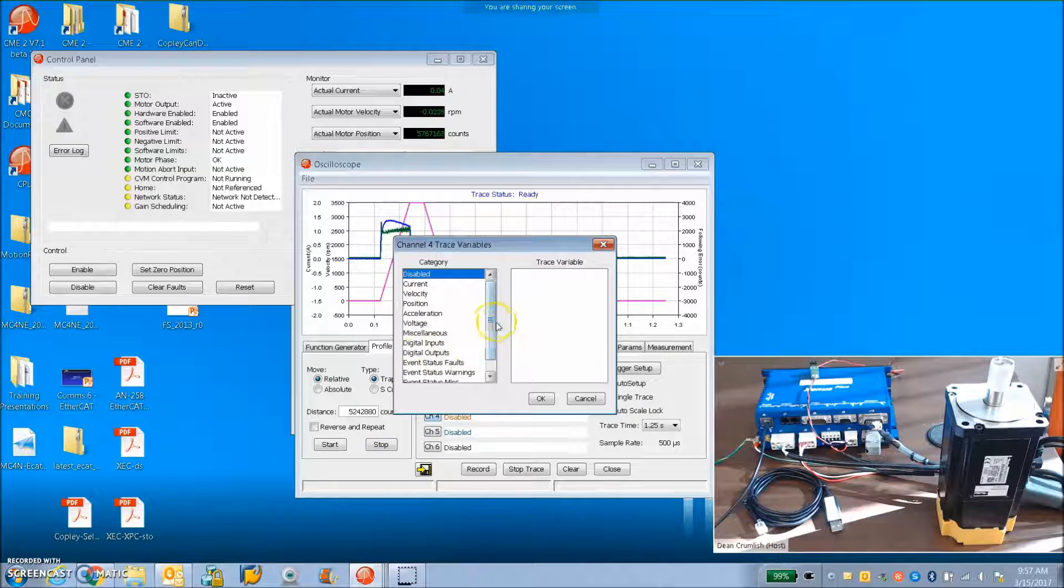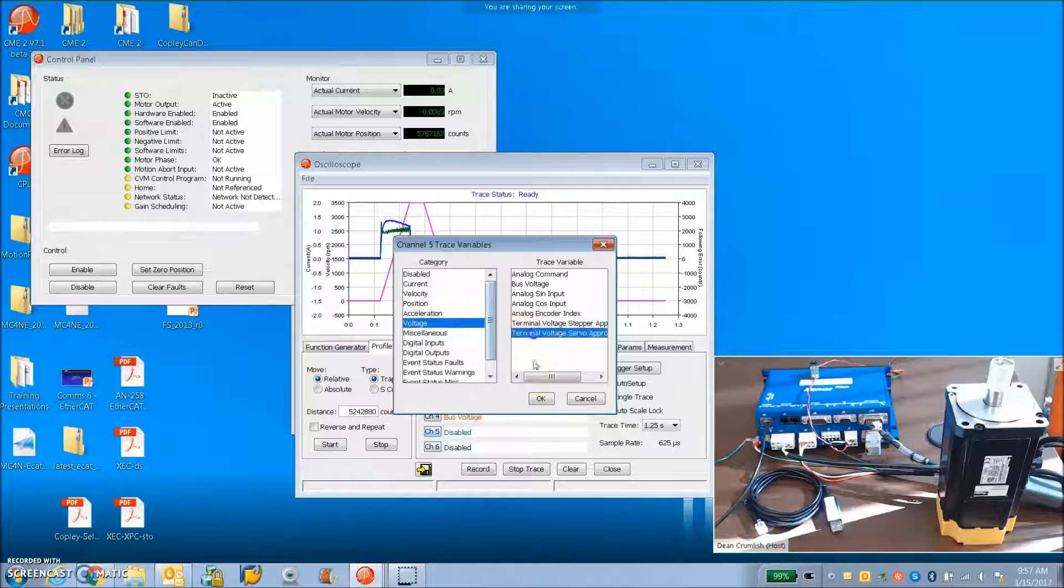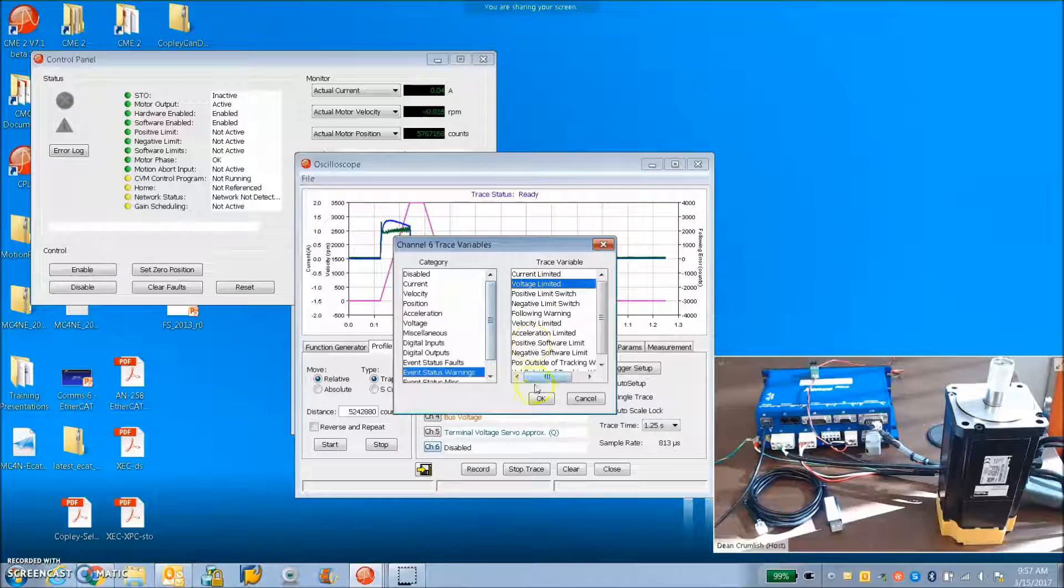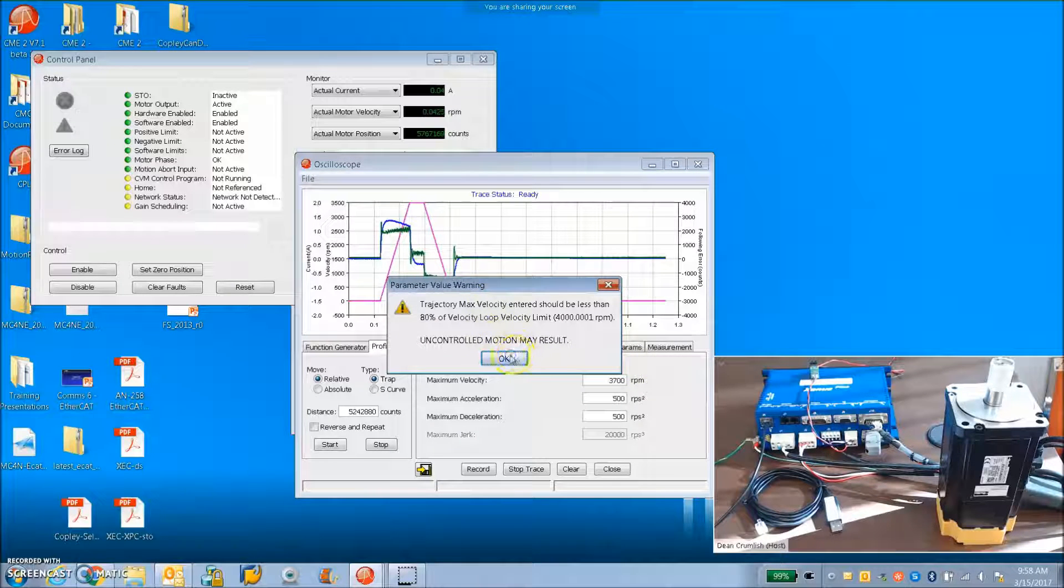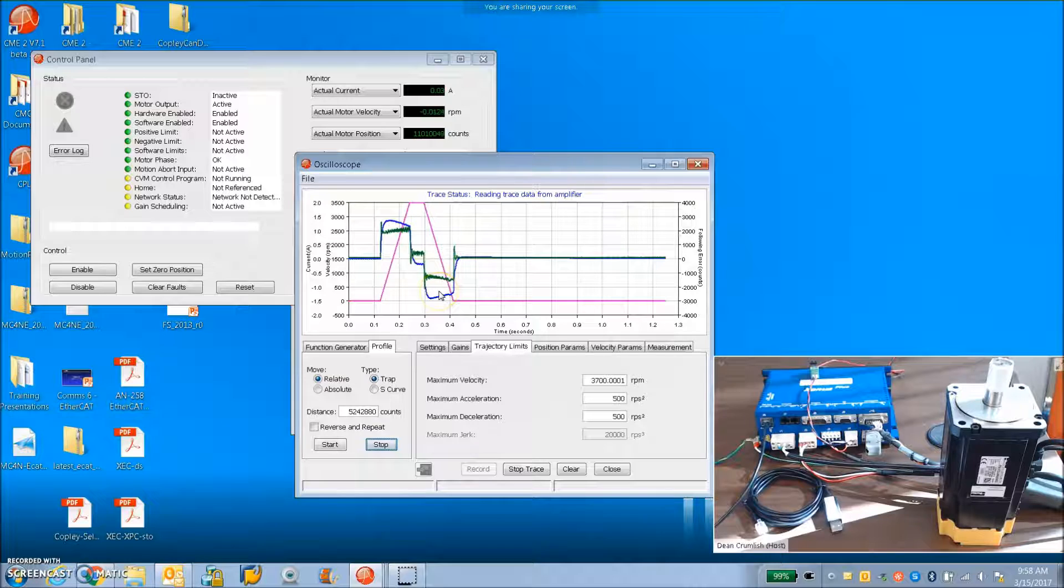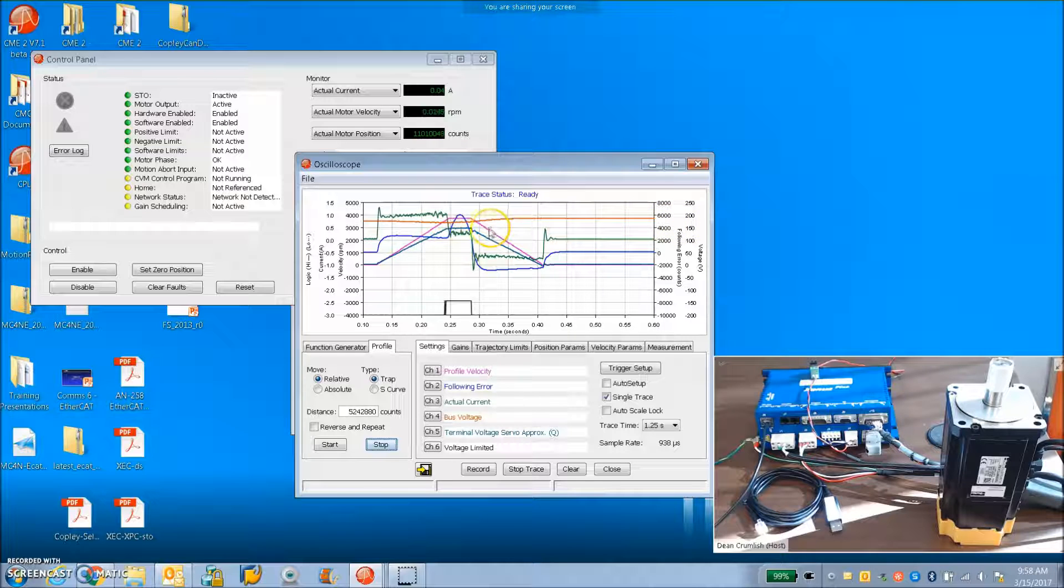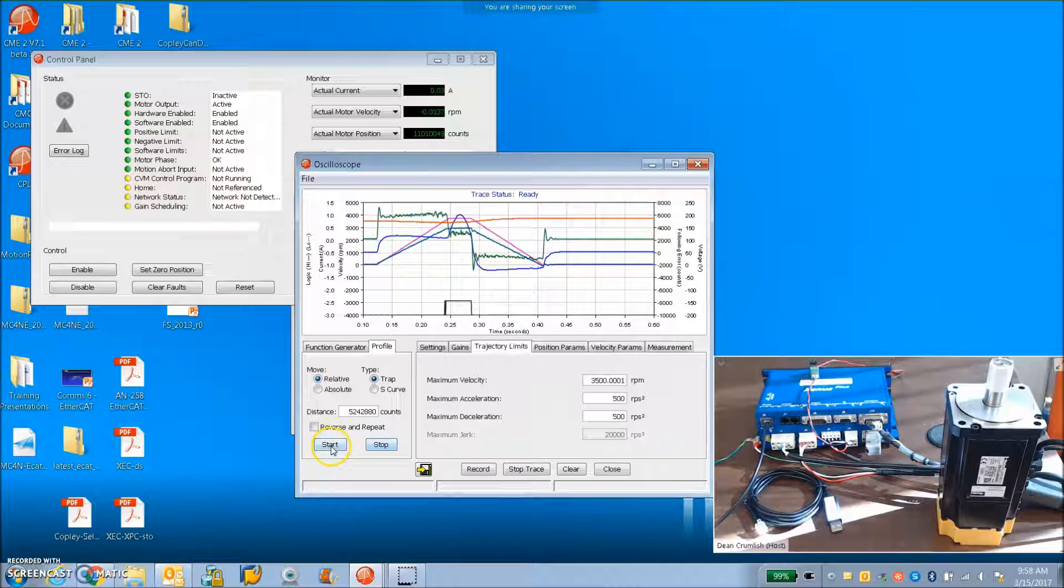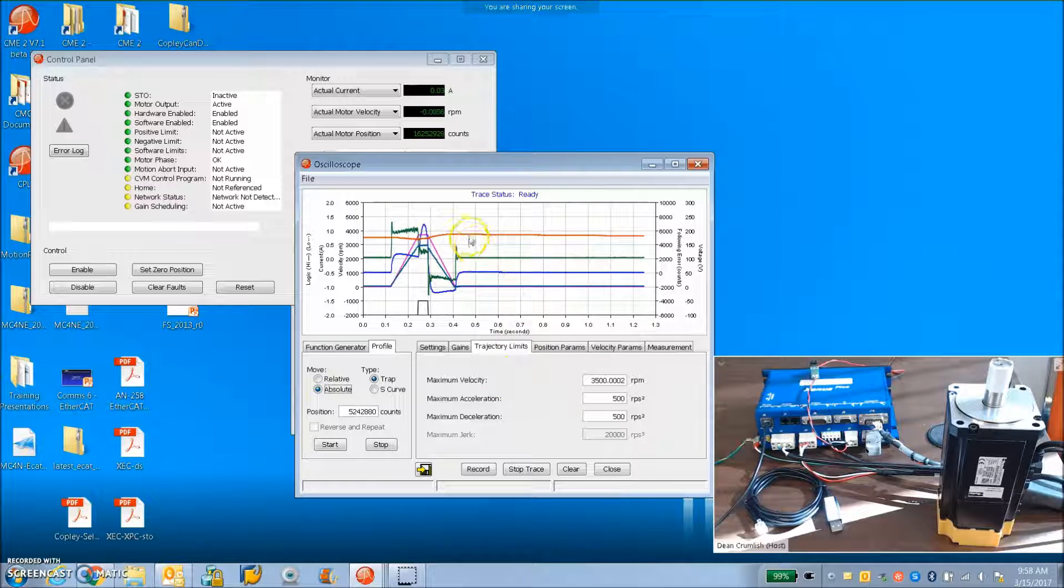We want to monitor the bus voltage. We got voltage bus. We're looking to see where we're going to hit a limit here. Monitor voltage terminal servo, that's the Q of the field-oriented control, and event warning voltage limited. I'm going to go 3,700. A little warning about my velocity limit there. Looks like we hit this speed but we're going to monitor the event of voltage limited. There's your power supply voltage in orange. You've drooped down a little bit from the rectified 120. You're going too fast. Your following error is growing. That's going to be a problem. You don't want a constant velocity limit warning. A little bump into it's fine at the end of accel or decel.